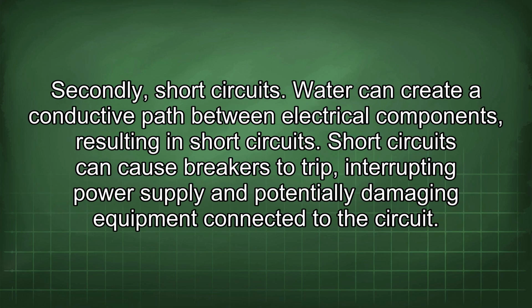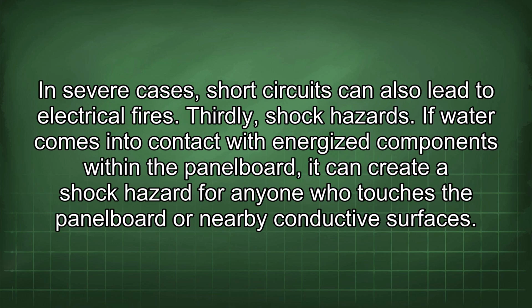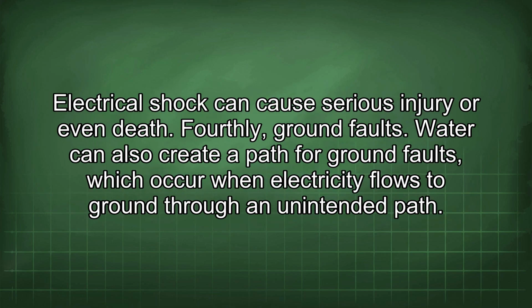Secondly, short circuits. Water can create a conductive path between electrical components, resulting in short circuits. Short circuits can cause breakers to trip, interrupting power supply and potentially damaging equipment connected to the circuit. In severe cases, short circuits can also lead to electrical fires. Thirdly, shock hazards. If water comes into contact with energized components within the panel board, it can create a shock hazard for anyone who touches the panel board or nearby conductive surfaces. Electrical shock can cause serious injury or even death.